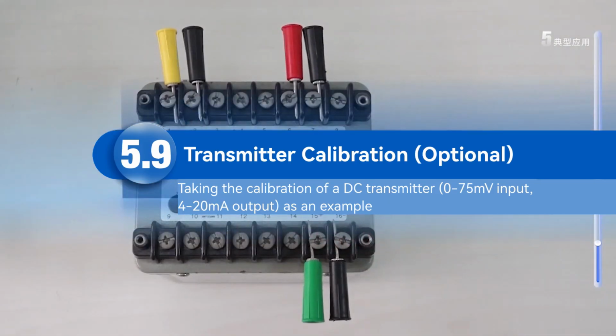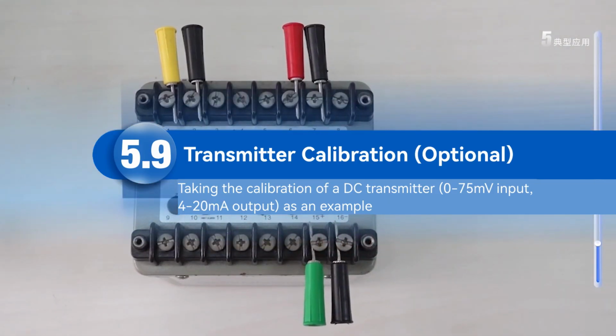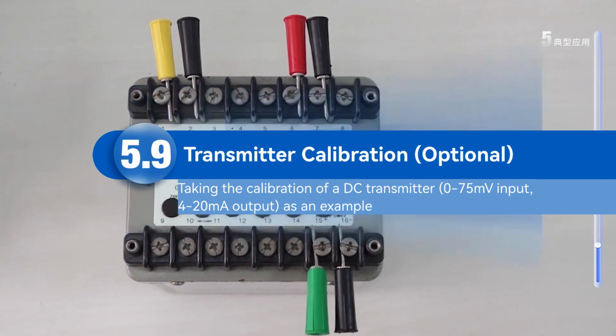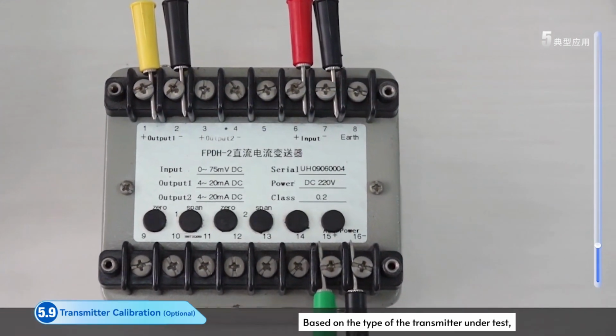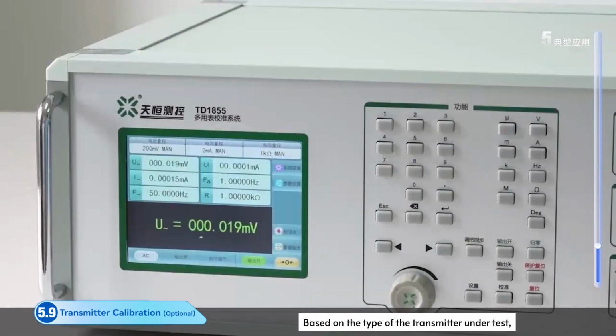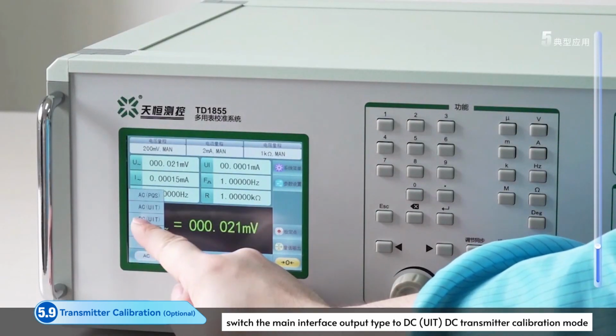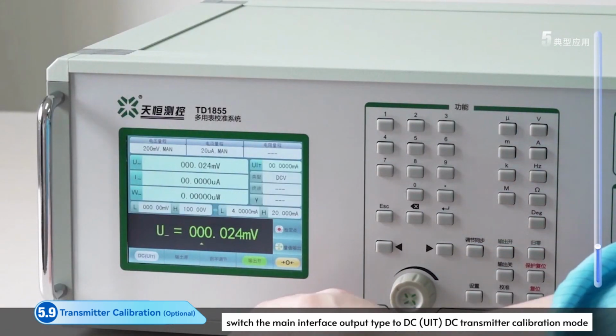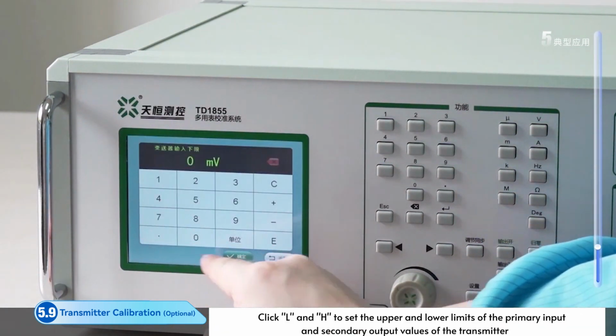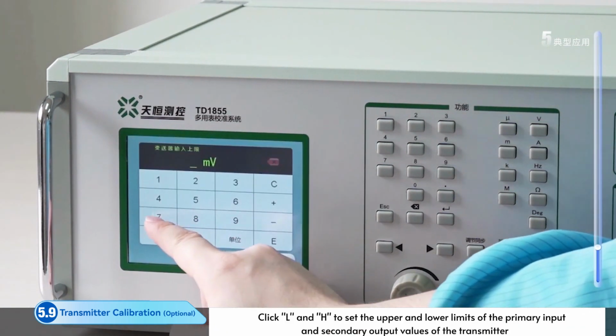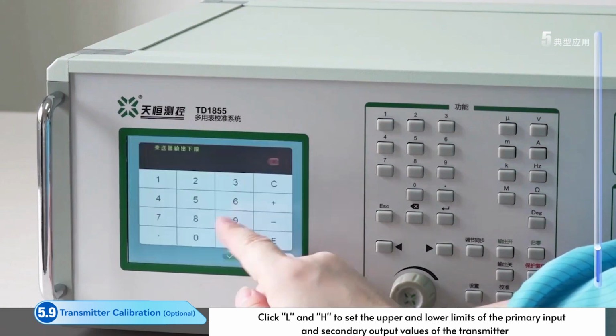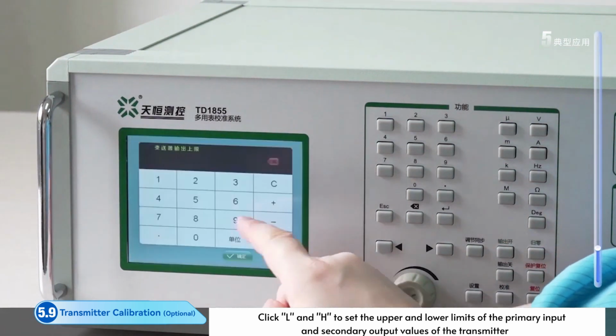Part 9. Transmitter Calibration. Optional function. Based on the type of the transmitter under test, switch the output type to DC UIT DC transmitter calibration mode. Click L and H to set the upper and lower limits of the primary input and secondary output values of the transmitter.